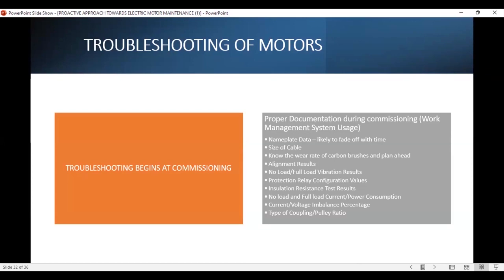And in case of wound rotor motors, the wear rate of the carbon brushes must be determined. So if it wears at this rate, you know when to change your carbon brushes. If you wait for your carbon brushes to wear out thoroughly, you end up losing your slip rings. So the carbon brushes wear rate has to be measured. Alignment results must be kept also in the work management system.